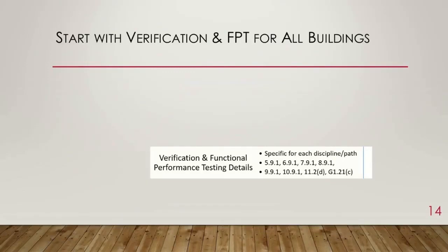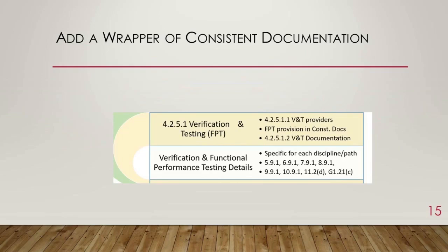Basically, to put it together, we've got verification and functional performance testing details. Those are included. Section 5 is envelope, 6 is mechanical, 7 is service hot water, 8 is our power systems, 9 is lighting, 10 is other systems, and then we've got our 2 performance sections. So those basic requirements say what needs to be tested, and then we again added a uniform up in the administrative section, uniform requirements about who are V&T providers, generally what qualifications, not a very detailed requirement set, I will admit, and that there be some functional performance testing provisions in the construction documents, and that there be a uniform basically structure for the verification and testing documentation.